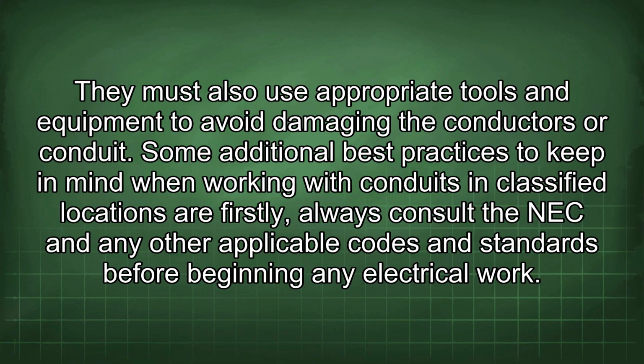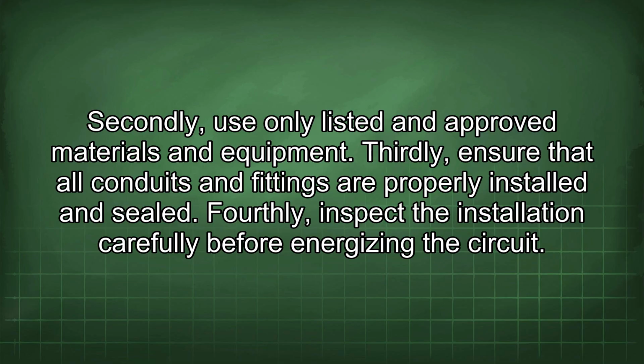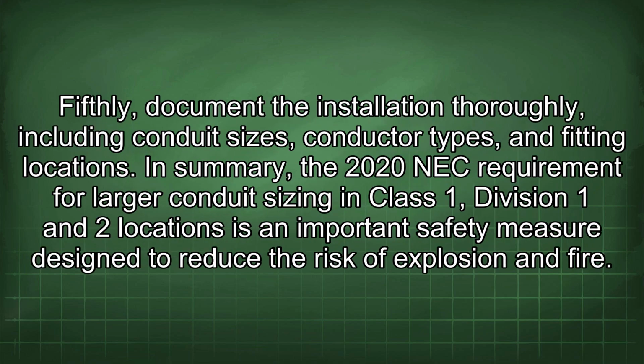Some additional best practices to keep in mind when working with conduits in classified locations are: firstly, always consult the NEC and any other applicable codes and standards before beginning any electrical work. Secondly, use only listed and approved materials and equipment. Thirdly, ensure that all conduits and fittings are properly installed and sealed. Fourthly, inspect the installation carefully before energizing the circuit. Fifthly, document the installation thoroughly, including conduit sizes, conductor types, and fitting locations.